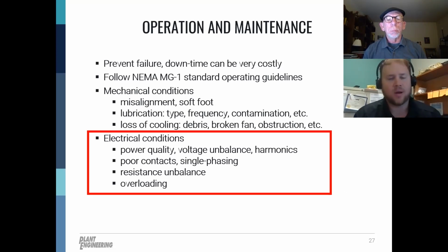So additionally, mechanical problems, keep the motor bearings well lubricated. Bearing failures, we covered, were the leading cause of motor failures. So how do you prevent the bearing failures? Well, grease the motor bearings at recommended manufacturer intervals. Be sure to use the proper type of grease and also the amount of grease they recommend. Don't over grease it. And if you have grease fittings on the drive-end and non-drive-end bearings, make sure you grease both of those. Some motors will have closed bearings, and so you may not see grease fittings. Those are bearings that come already with grease preloaded.